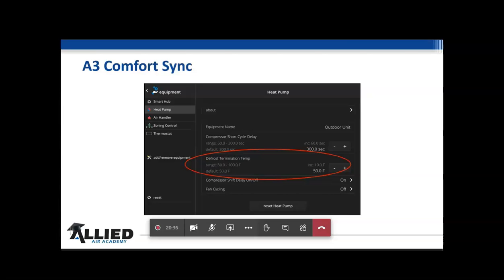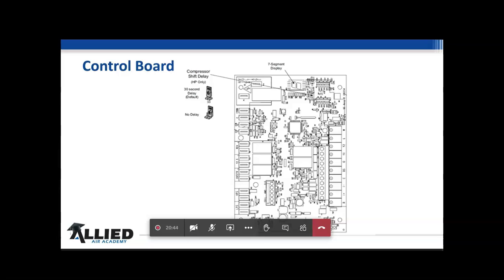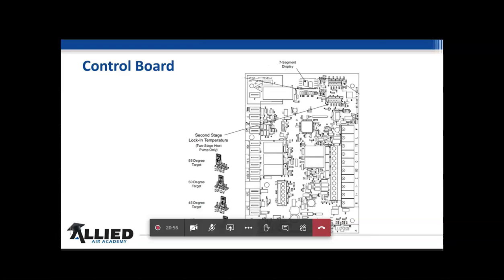Those are some of the easy ways. Now, I mentioned that if they use a conventional stat, they're going to have to make all these adjustments on the board. So I just want to point out a few things on the board here. You still have the compressor shift delay. Not a big deal. Everybody's going to leave that on there. Here's your second stage lock-in temperature, two-stage heat pump only. You got 55, 50, 45, 40. Again, if you set it here, your target's only going to be 55 degrees if you use it on the board. Keep that in mind too.